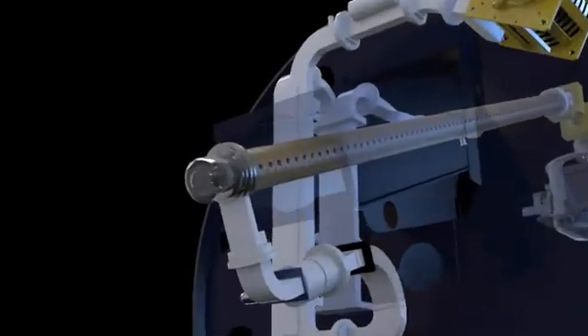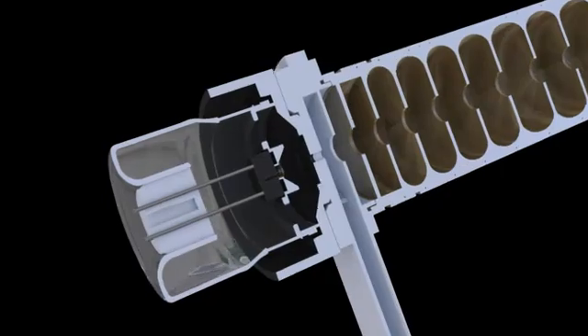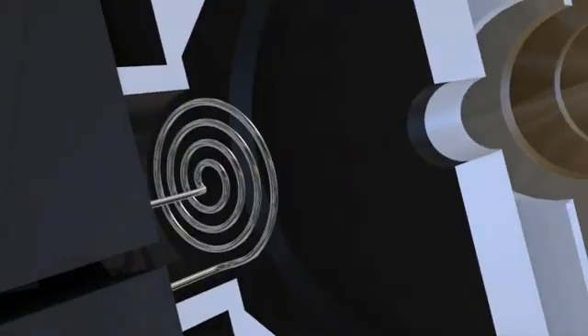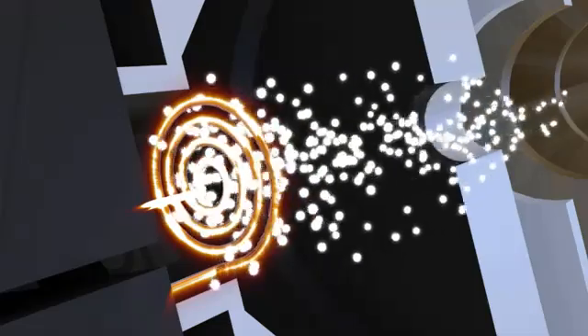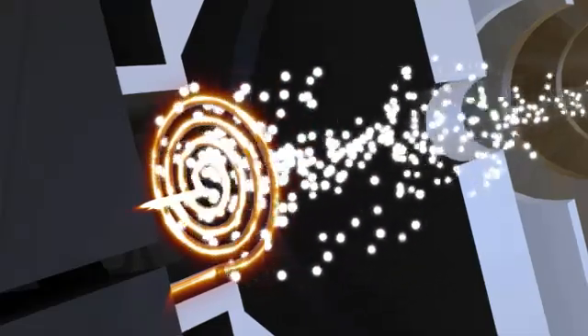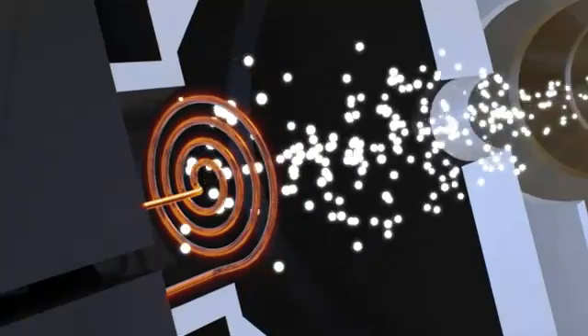The digital accelerator uses a diode type electron gun situated at the end of the waveguide. The electrons are produced by heating the tungsten filament within the cathode and are then injected into the waveguide. The number of electrons injected is controlled by the temperature of the filament.